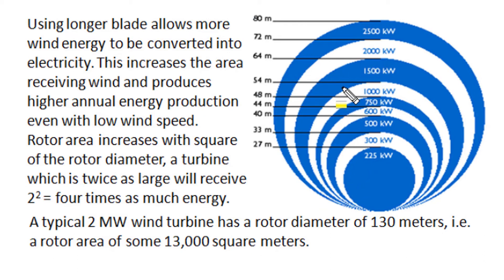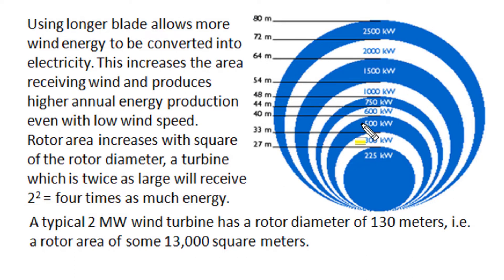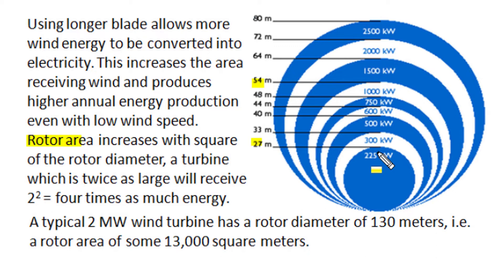Use of longer blades on a turbine allows more sweeping area of turbine blade rotation, enabling more wind energy to be converted into electrical output. A higher sweep area can produce higher annual energy production even with low wind speeds. Rotor area increases as the square of rotor diameter — so if we double the rotor diameter, the electrical output becomes four times.